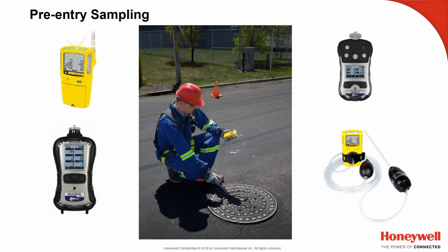These are the type of monitors. Even a diffusion monitor equipped with a hand aspirator can get it done. We know people are still lowering the monitor into the confined space. The danger is damaging it, getting into a dark area, and then getting it into water, and rarely is it distilled water. It could be sewage water, causing permanent or temporary damage to that instrument. So best practice would be to have a pumped unit with a catch or a hydrophobic filter, like you see here on the back of the Max XT2, which would prevent water from getting inside the instrument.